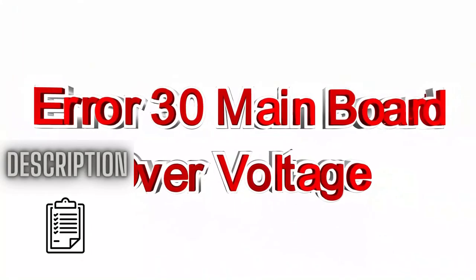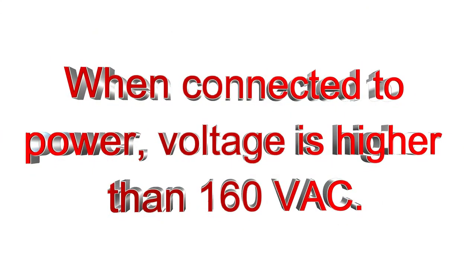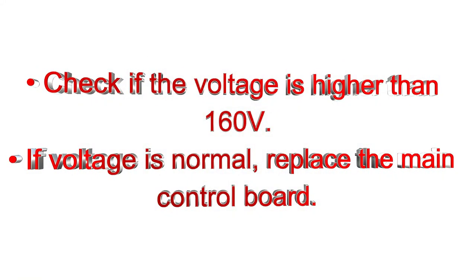Error 30, main board over voltage. When connected to power, voltage is higher than 160 VAC. Check if the voltage is higher than 160 V. If voltage is normal, replace the main control board.